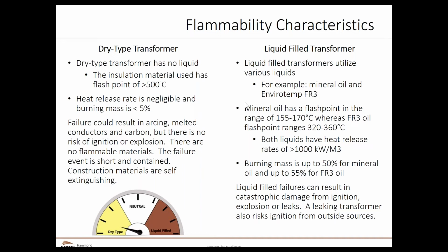Obviously, we have to be very concerned during a short circuit, for instance, to make sure that there's nobody by the transformer, because short circuit conditions can send out gases and stuff like that. So we're not saying you want to be staying next to a transformer by any stretch of imagination, dry or liquid, if it fails. But the failure mode of a dry type is much more benign than a liquid filled.